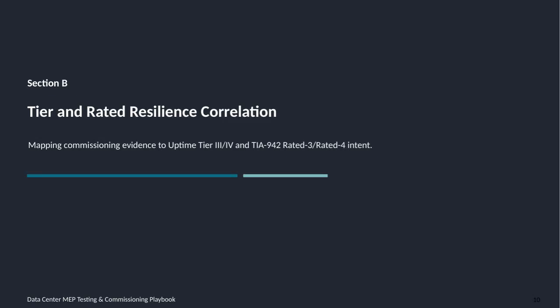Now, we're moving into Section B, where we'll explore the correlation between tiers and rated resilience. This part focuses on how commissioning evidence aligns with the intent of Uptime Tier 3 and 4, as well as TIA 942 rated 3 and rated 4 standards. Essentially, we're mapping the testing and commissioning data to ensure these resilience levels are properly met. This approach is detailed in the Data Center MEP Testing and Commissioning Playbook, which serves as a guide to confirm that infrastructure performance matches the required tier and rated criteria. Understanding this correlation is key to maintaining robust and reliable data center operations.